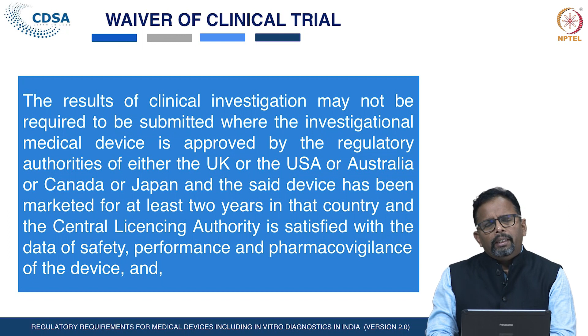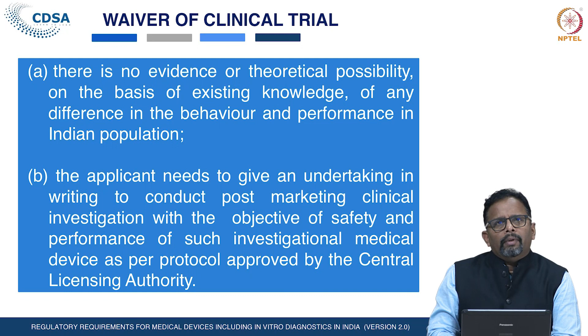The applicant needs to give an undertaking in writing to conduct the post-market clinical investigation with the objective of the safety and the performance of such investigational medical devices as per protocol approved by the Central Licensing Authority. So, in such cases, the requirement of the clinical investigation may be waived off.